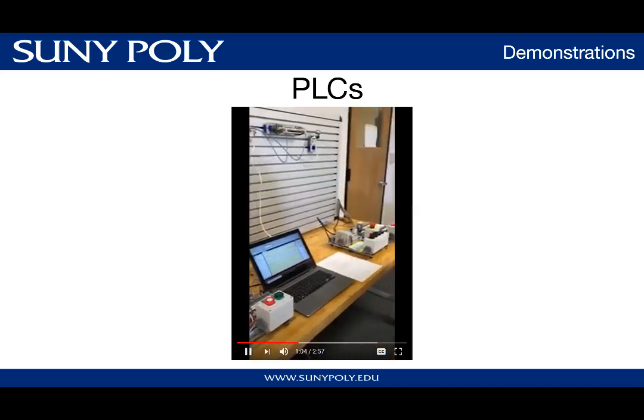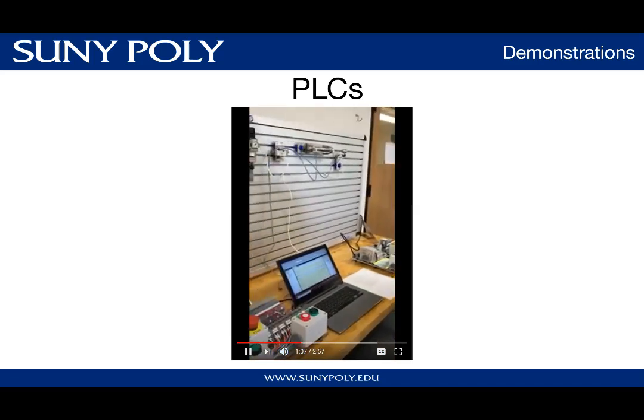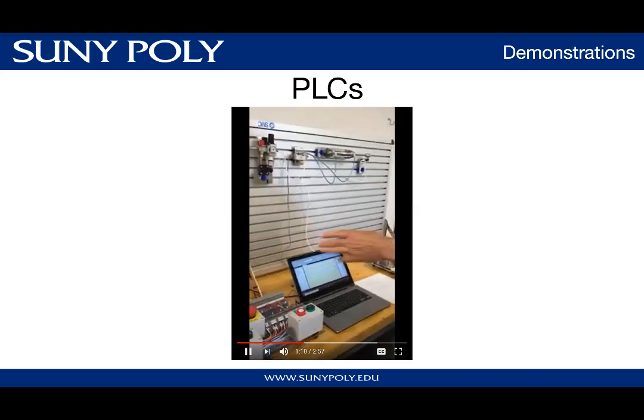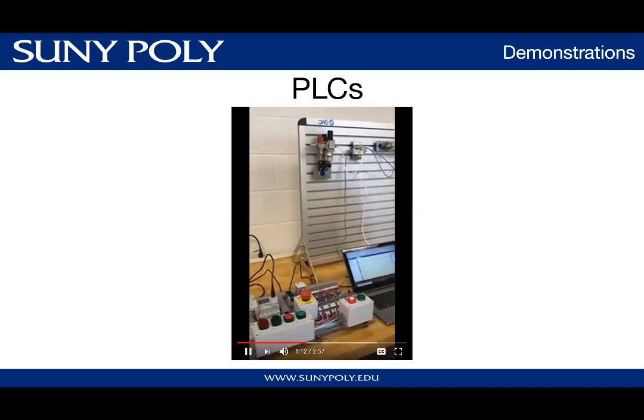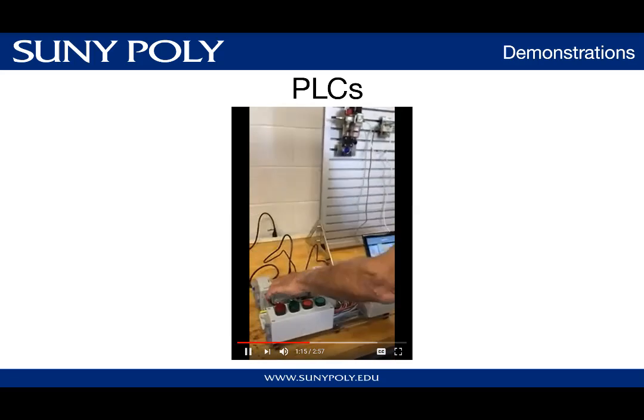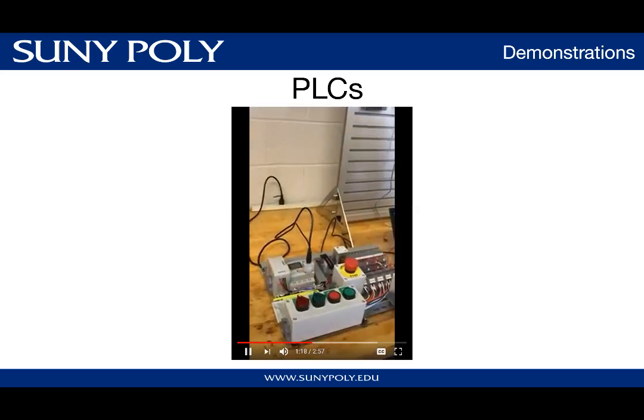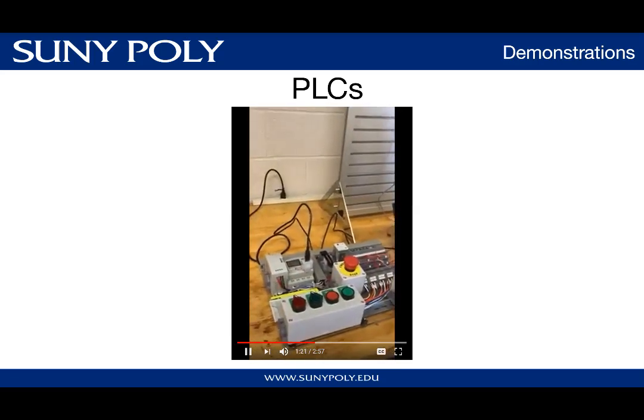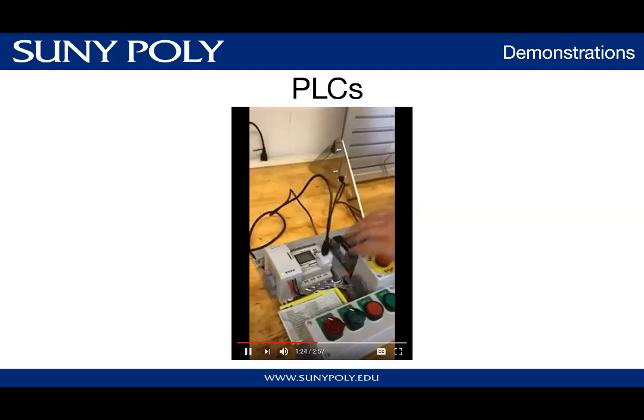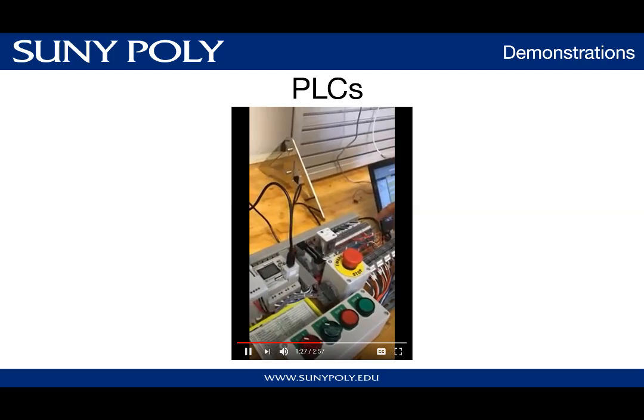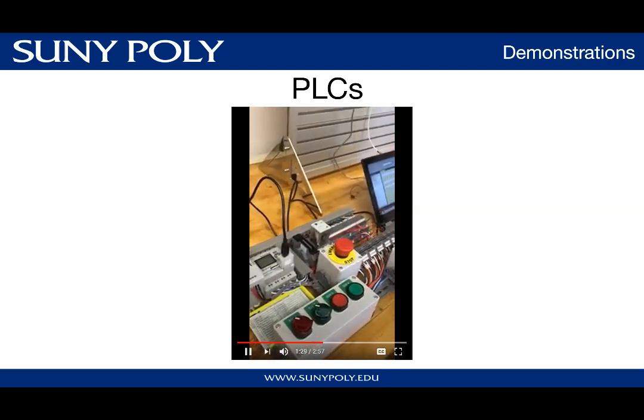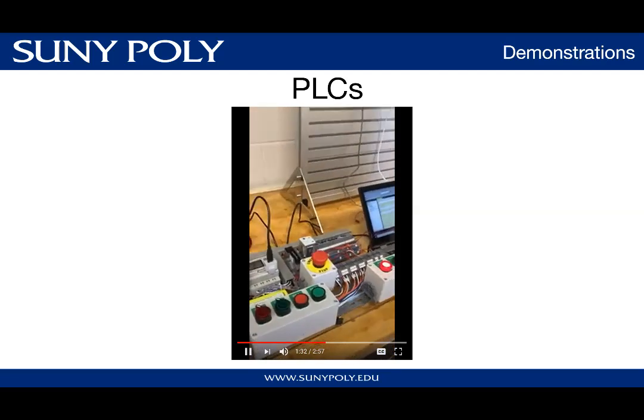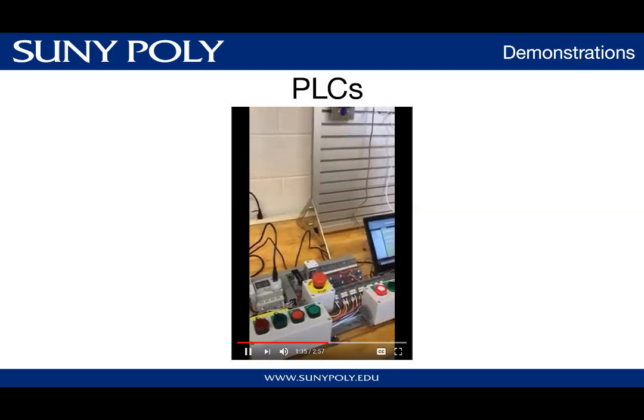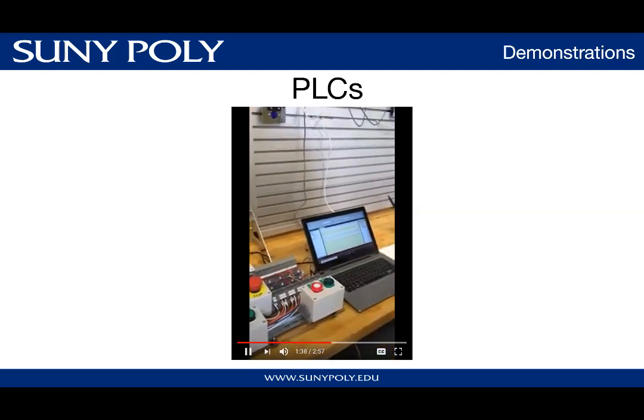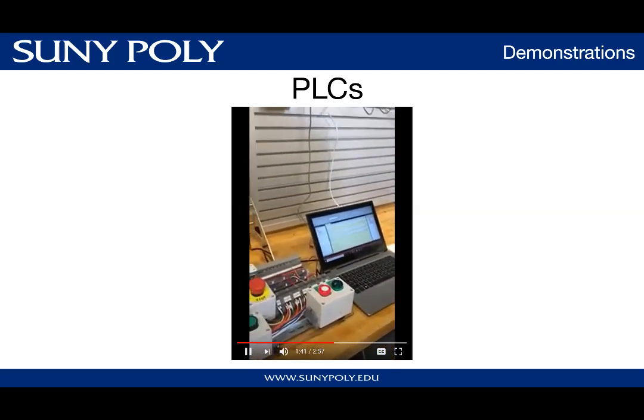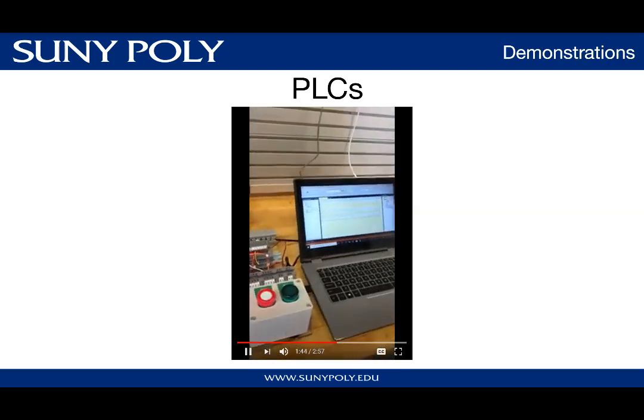We talk about single block versus rack-mounted PLCs that are used in the mechatronics training. This particular arrangement uses the matching 24-volt DC power supply that goes with the PLC, although a separate 24-volt supply could be used. This supply also supplies up to 1.6 amps of current for the system here, for other connections and to run the peripheral devices. As I mentioned, the programming software is free, so there's no subscription required, and participants could actually download this to a laptop if they chose to.